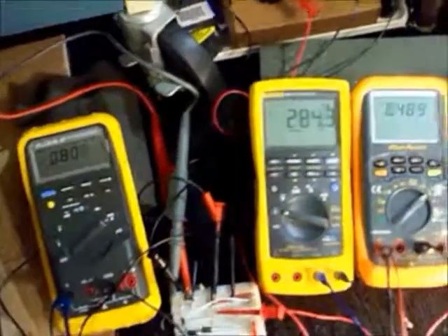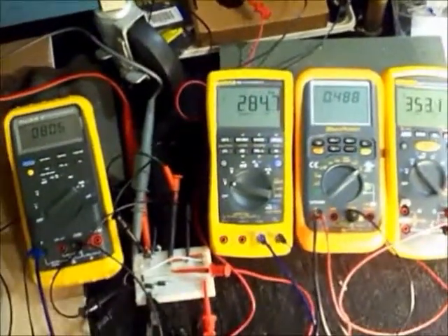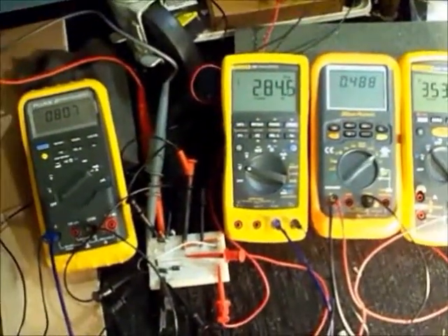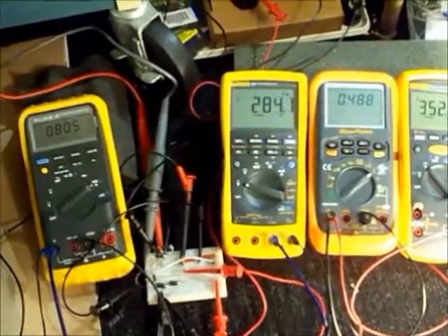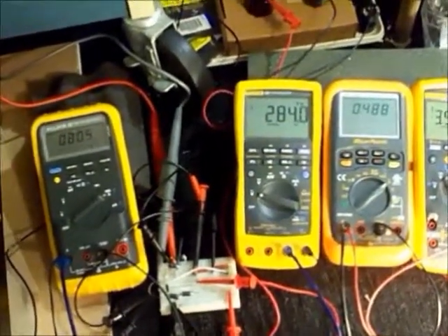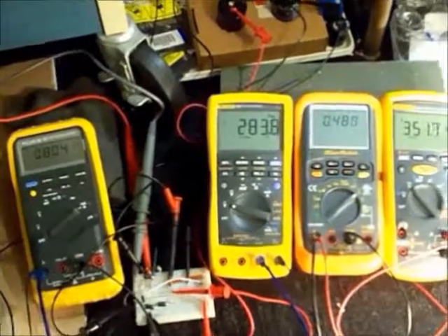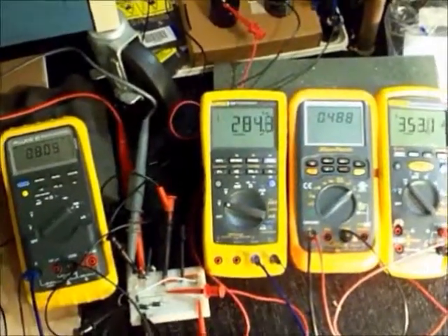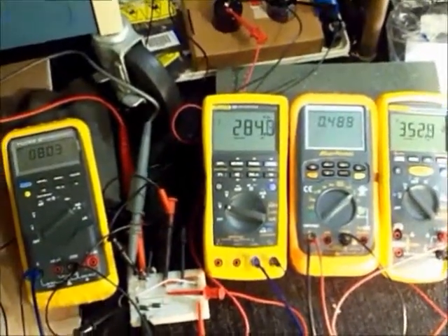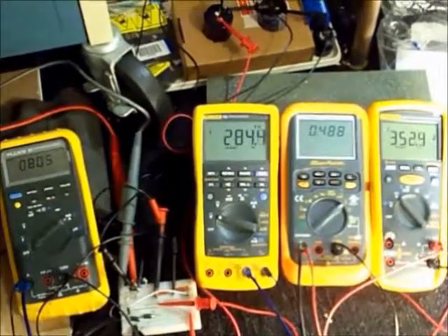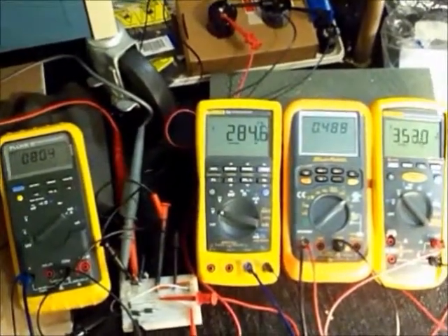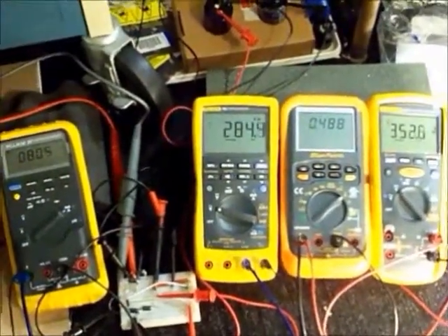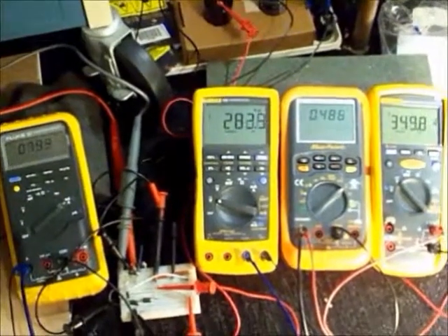So let me maybe put a smaller load on this thing so we can get that AC current down to about 300 milliamps, and at that point we should be holding 300 volts, which is what the data plate on the transformer states. If that's the case, we've got a good transformer. So stand by.